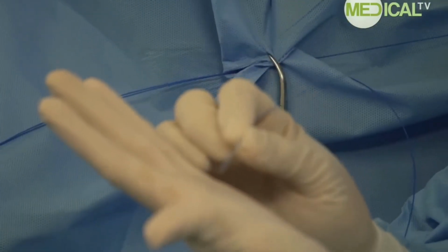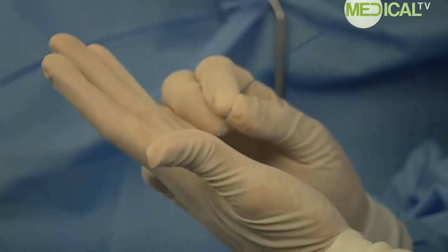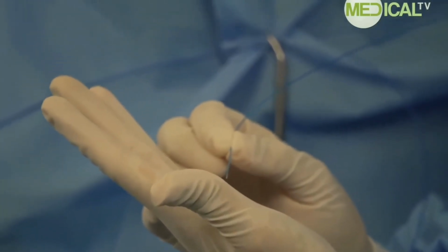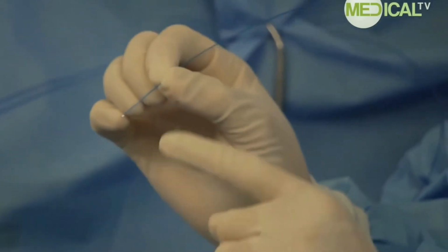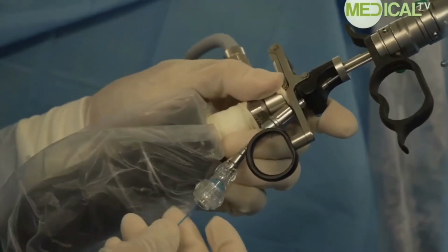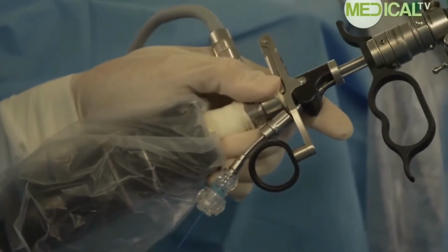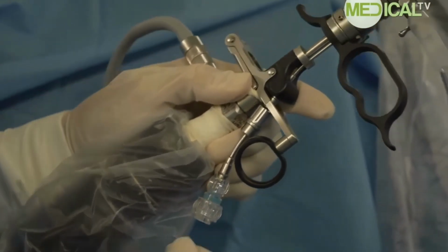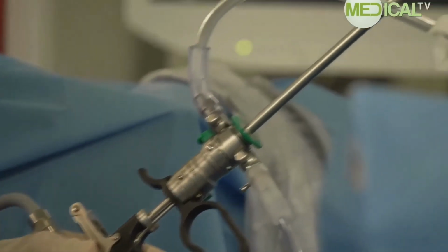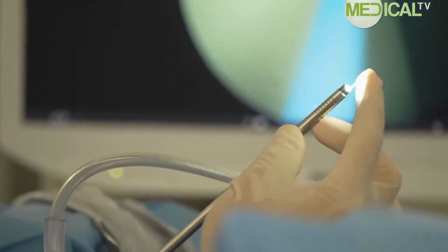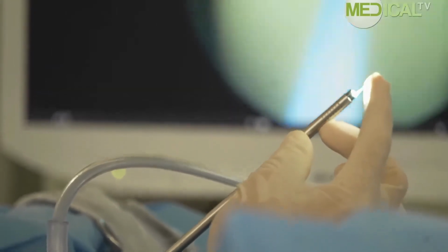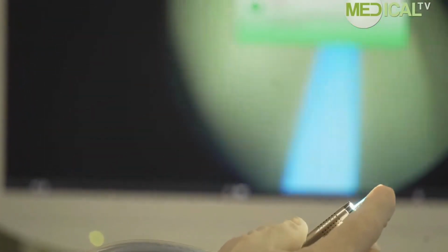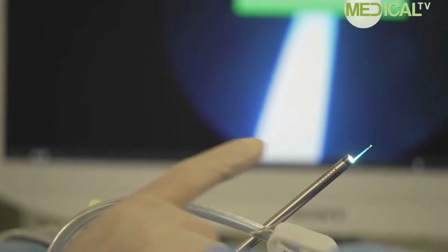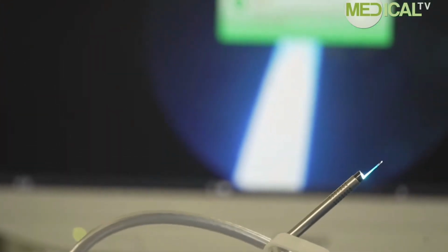The fiber measures 550 micrometers, or 0.55 millimeters, which is approximately half a millimeter. This fiber carries the laser's 100 watts. This fiber will be inserted into the working channel and we'll observe the white light show up at the device's end. See? This fiber is displayed on the screen. All of our actions are performed with a clear view provided by the magnification from our micro camera.